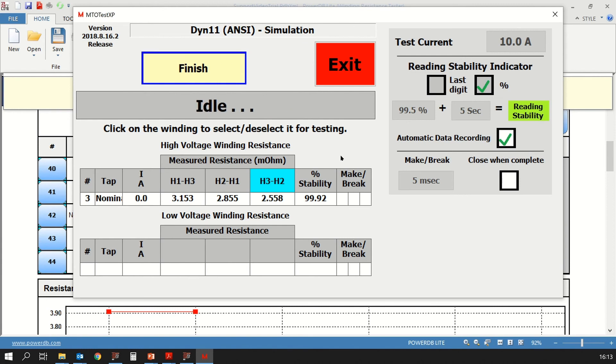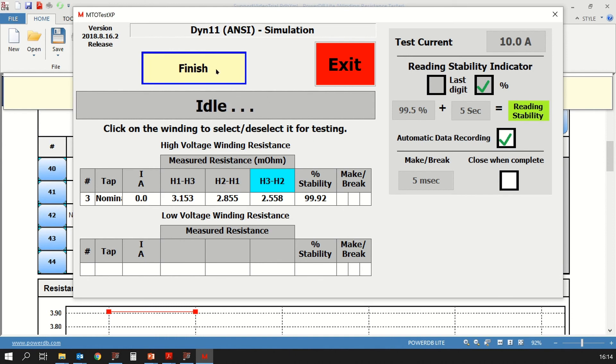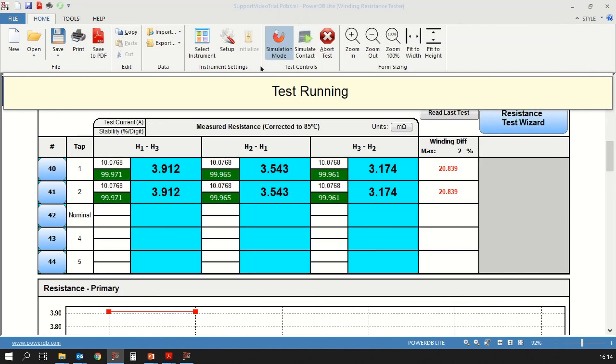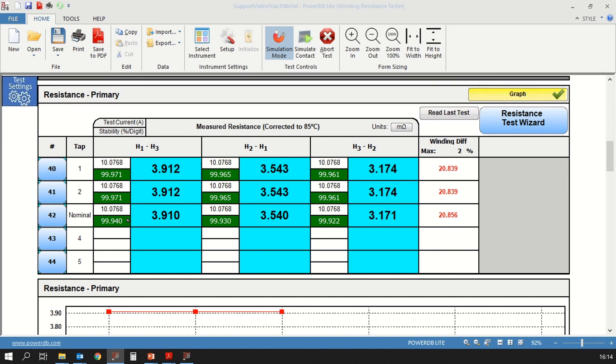The testing has now completed. All three phases have been tested with the appropriate reading stability. Once this screen is reached where you have measurements for all phases, then you can click on finish. Once you click on that, the values are now updated in the form. You can see that the line item 42 has updated values for resistance. They have the test current that was used and the stability for each reading. That's how you would conduct a winding resistance quick test.